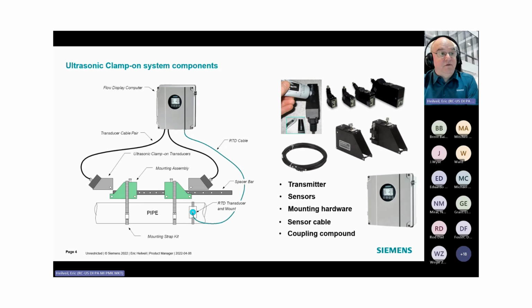And that's great. And what do these things really look like when you're not talking about a cartoon diagram? These are real actual components. The transducers, as you can see, can be quite small for small thin-walled pipes, and can be quite large for the larger, thicker walled pipes. And the reason for that is that just like a bell, you would not have a very small clangor on a very large bell. You would need a larger gong or clangor on them in order for them to work appropriately. So that's what these are for. So the bigger the thicker the pipe, the larger the transducer that's needed.